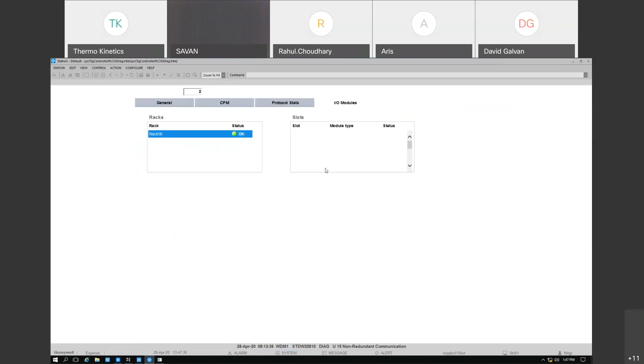The integration is okay, meaning that this is important. If this LED was to be red, that would mean that somebody made a change in the logic of that PLC and did not publish it to Experion. So you may have an inconsistency there. That's what that means. So right now, consistency is great. It's green. Memory usage and storage, your Ethernet links and all this good stuff, your power supply modules, protocol statistics, and then your I/O modules diagnostics as well, like what I showed you in the first splash screen.